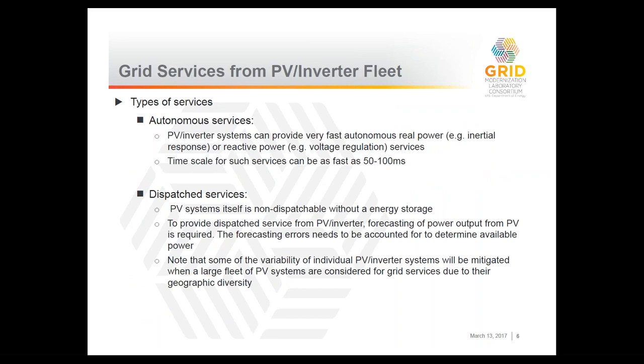Now, how can these inverters provide grid services, especially for the PV case? There are two types of services this inverter can provide. One is the autonomous service. For example, a PV inverter system can provide very fast autonomous real power, such as inertial response, or reactive power, such as voltage regulation services. The time scale for such services can be very fast, because we have this fast inverter interface. That is more or less common, and it is getting implemented right now in some territories, such as California and Hawaii, but it will get more and more common in all other 50 states in the United States very soon.